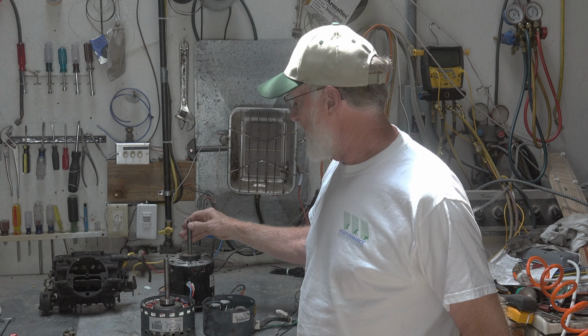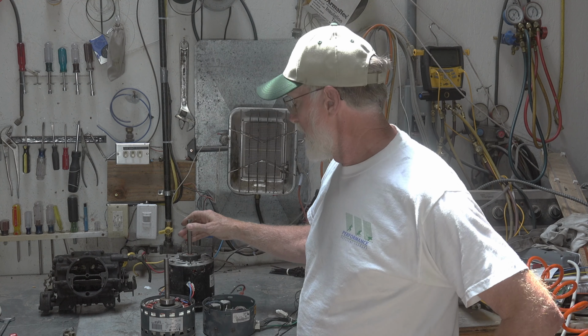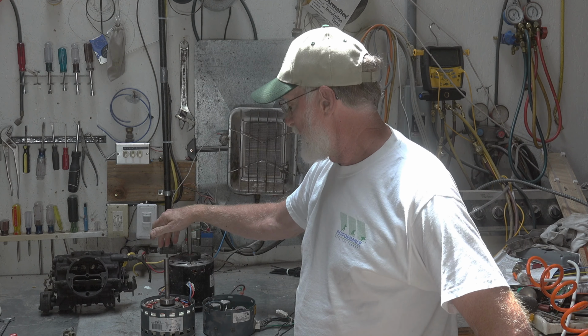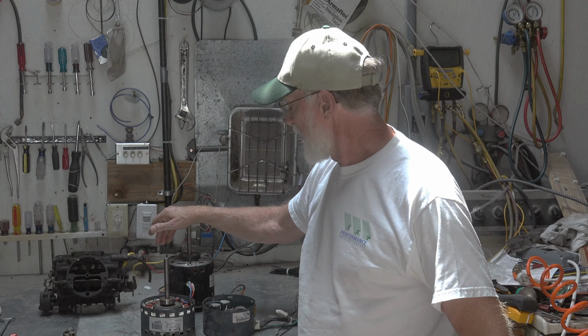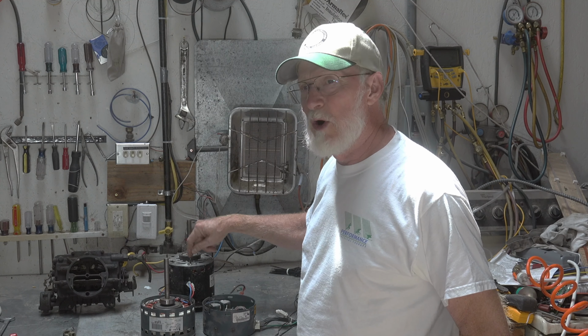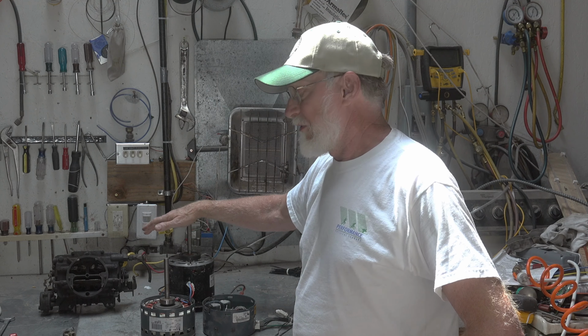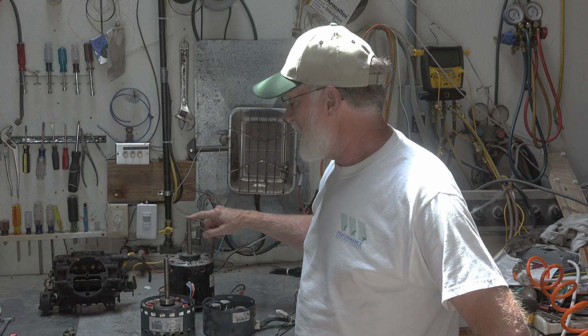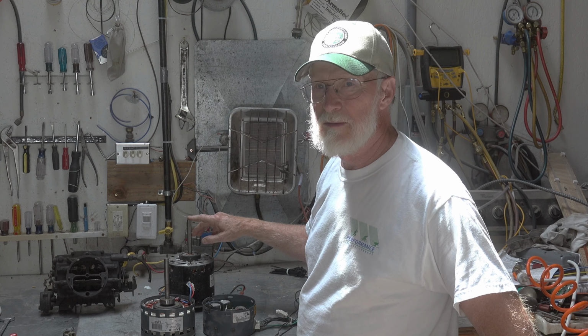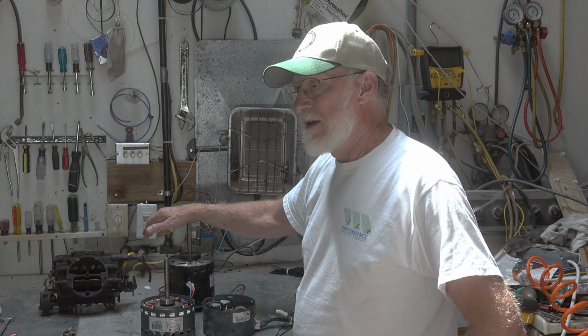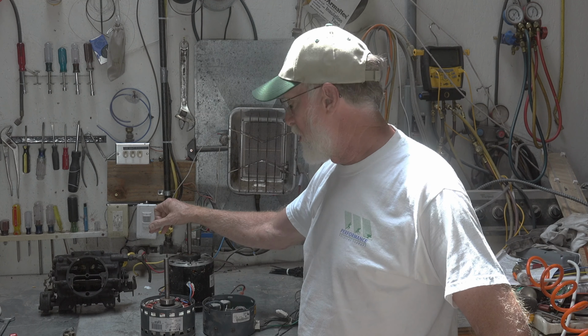Okay. The PSC motor is similar to this because what it does is it runs at one speed. Now, I know you're going to say, no, it doesn't, but we'll talk about that. This is a synchronous motor, not counting slip. If I have 60 cycles per second in my AC power, this thing is going to travel at a specific speed, depending on the number of poles in the motor.